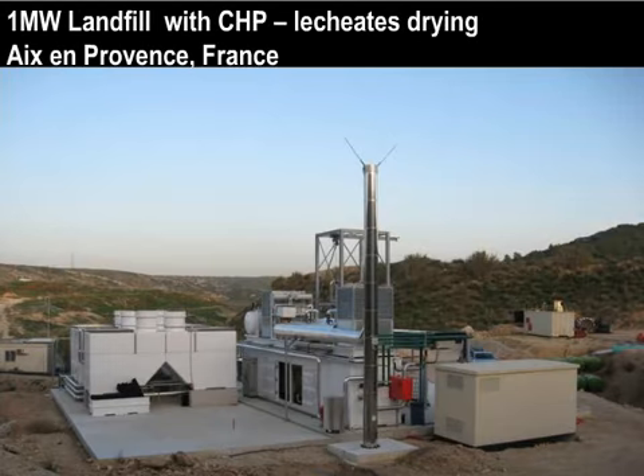Its example is from Aix-en-Provence, France, and in this 1 megawatt landfill application, the heat is used to produce hot water, and this hot water will actually dry the leachates. The leachates is the liquid that is remaining at the bottom of the landfill that has to be pumped, and prior to transport, they would raise the concentration of these leachates to reduce the transportation cost, and they use the free heat of the landfill genset here.